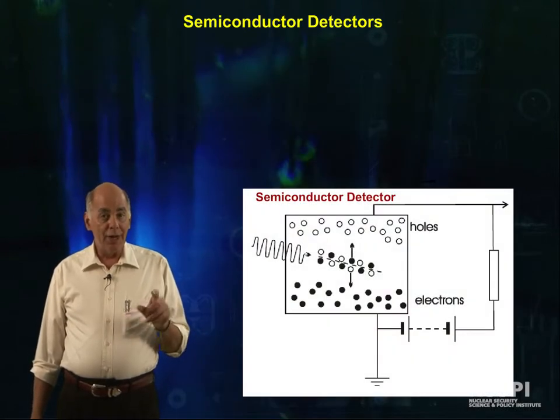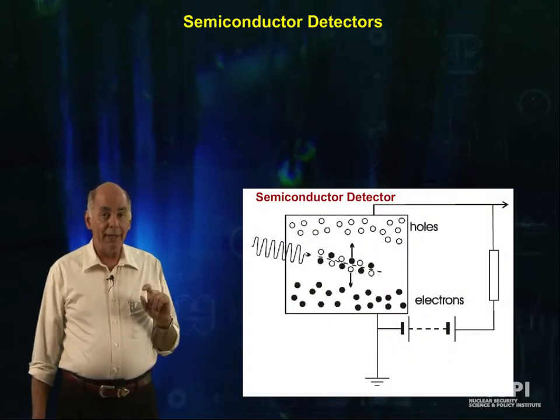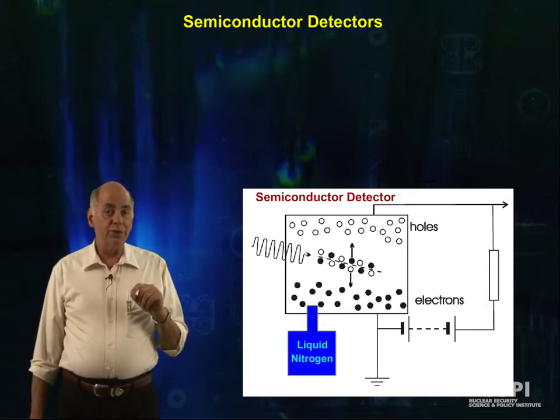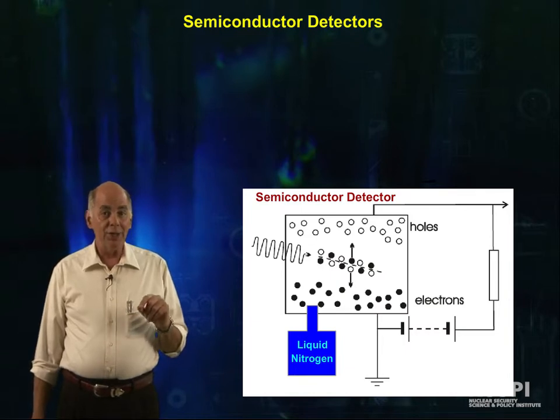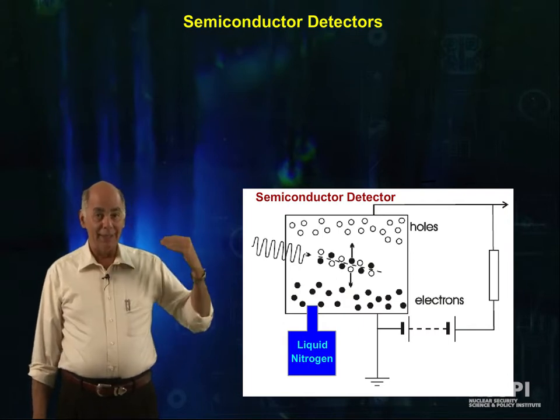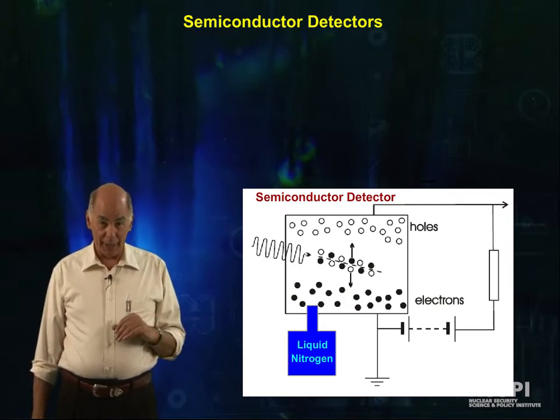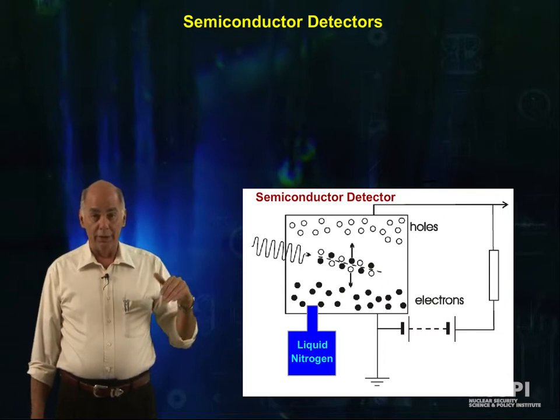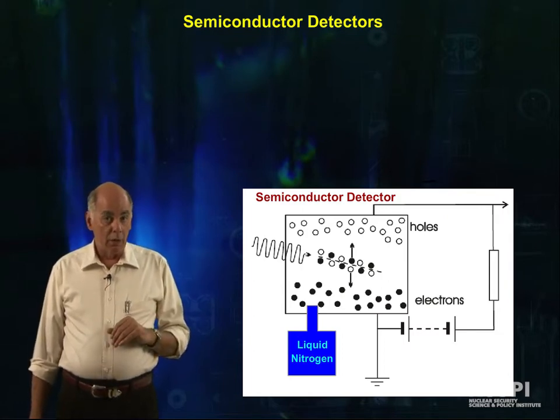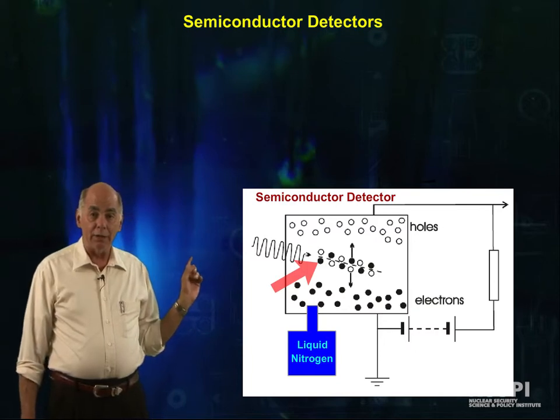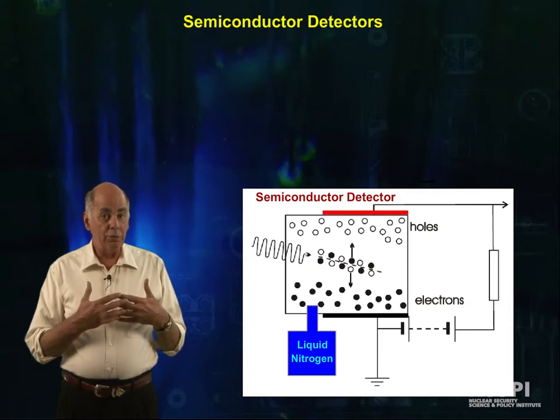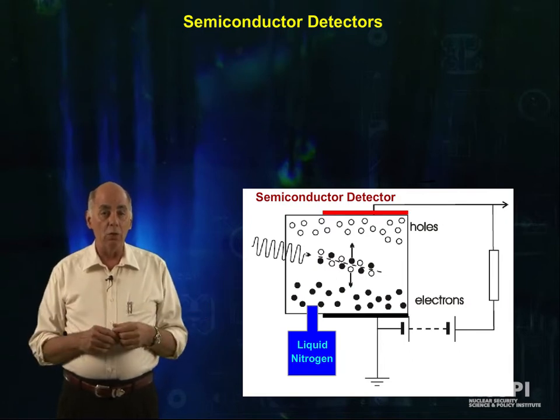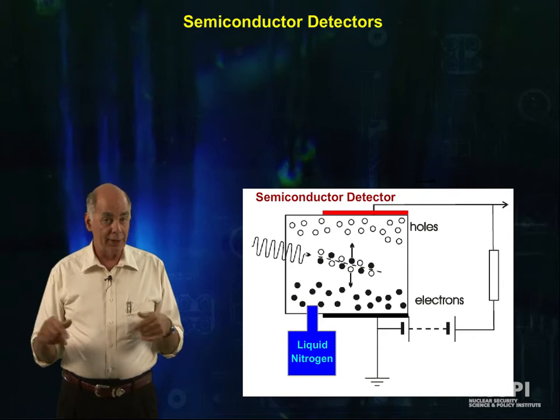We can exploit this narrow band gap to make a radiation detector. If we cool the semiconducting material down to liquid nitrogen temperatures, the conduction band will be empty because thermal energies are now too low to kick the electrons into the conduction band, and the conduction band quickly drains of electrons. Radiation interacting in the semiconductor can promote electrons into the conduction band. An applied voltage will sweep these electrons and the holes left by these missing electrons out of the detector.